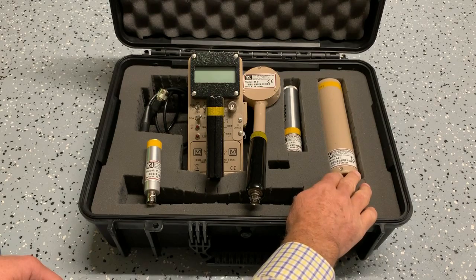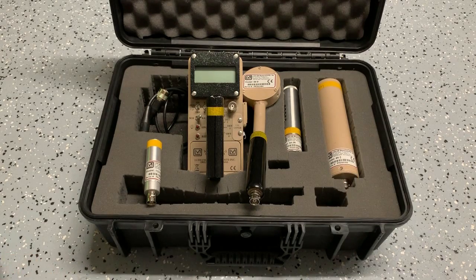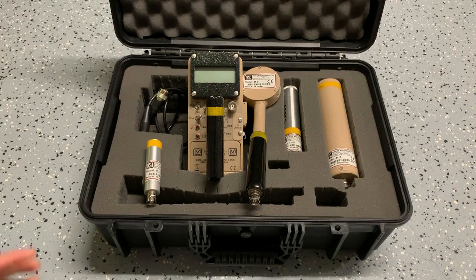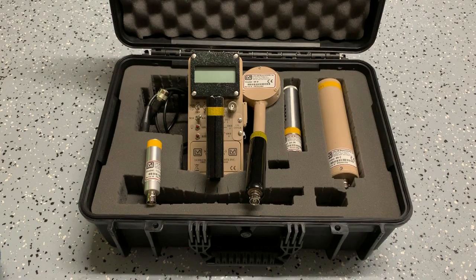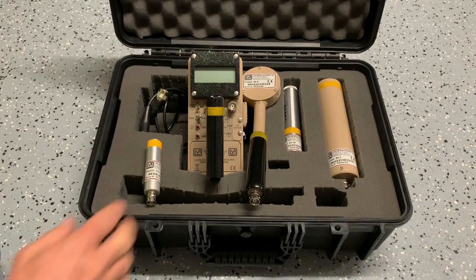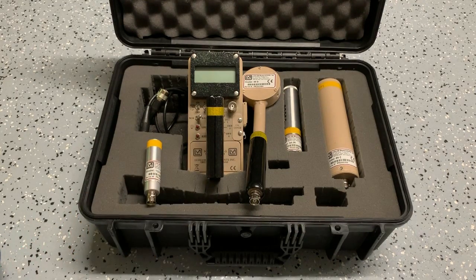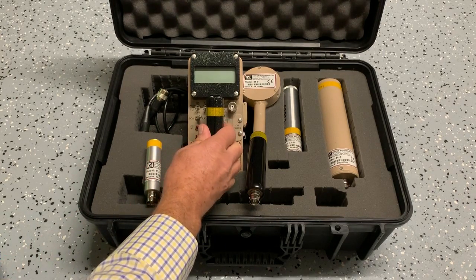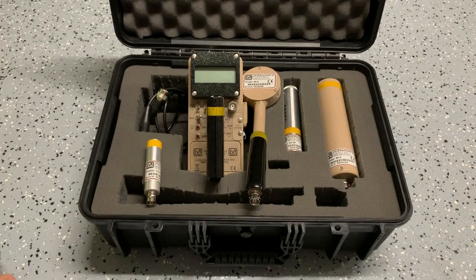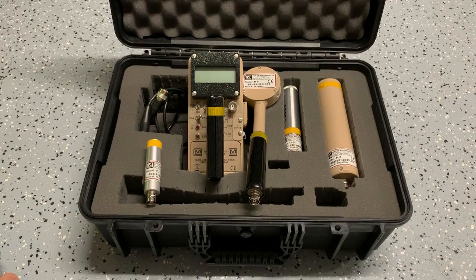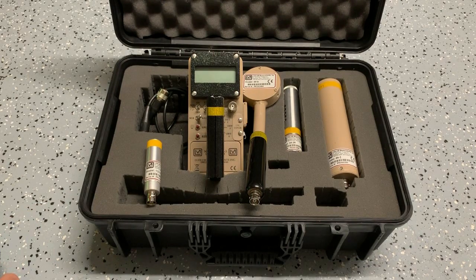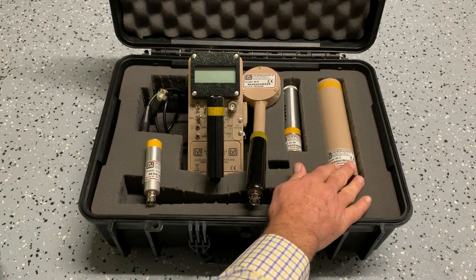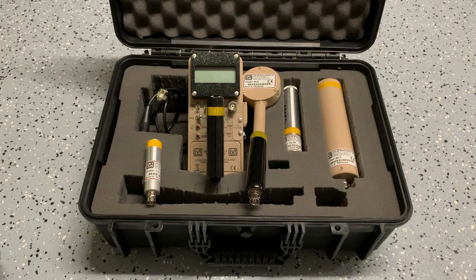But specifically I'm going to be talking about this probe and one of the things that we see with that is that its range is really limited to about 50 mR per hour when hooked to a digital rate meter like this. A lot of people don't realize that because this rate meter is capable of displaying and will auto-range up to 9,999 R per hour. But if I have this probe attached, it's really only good to about 50 mR per hour.